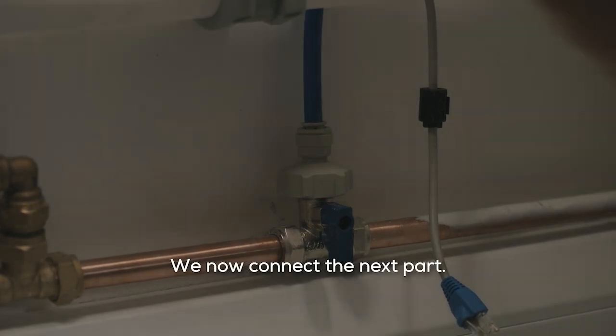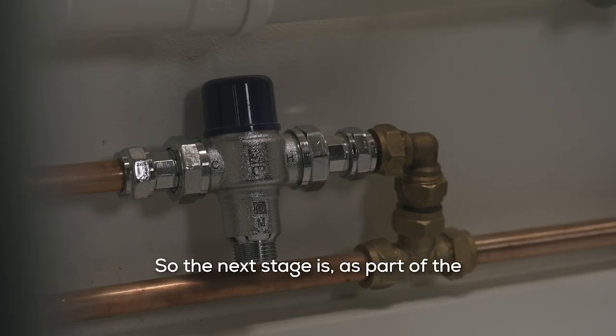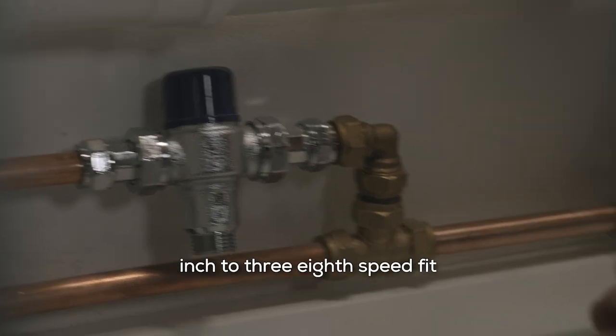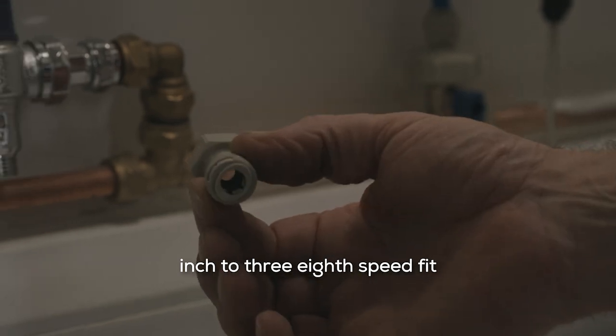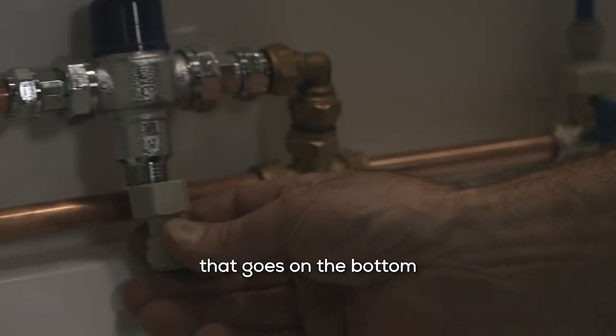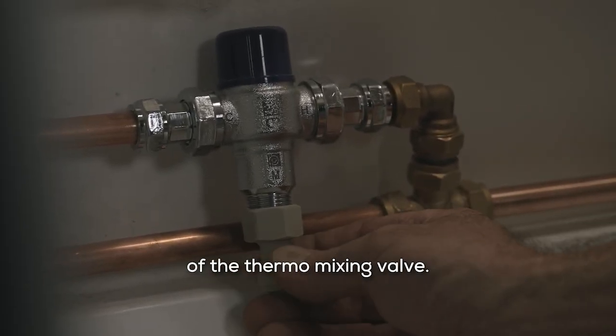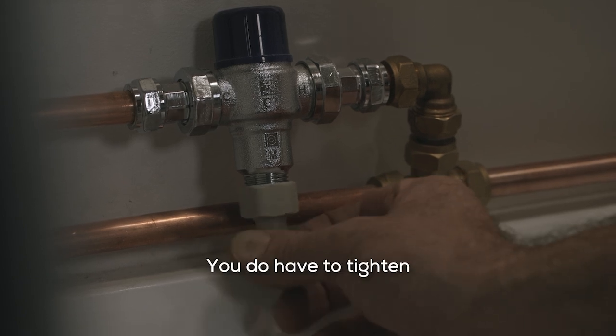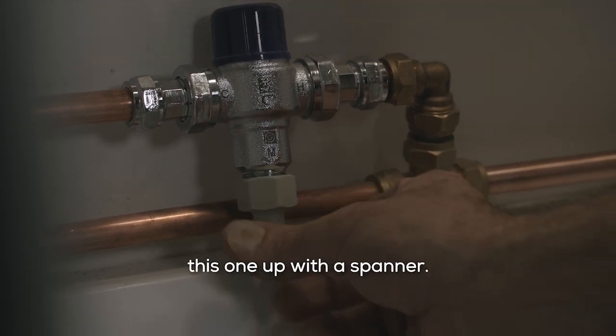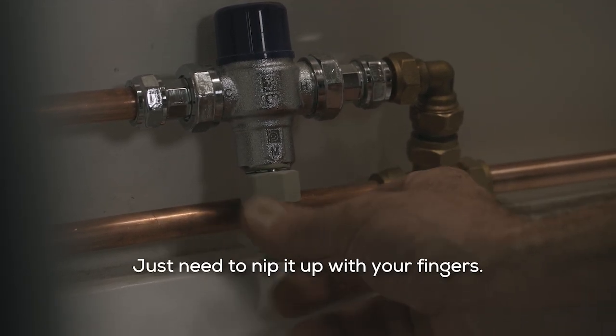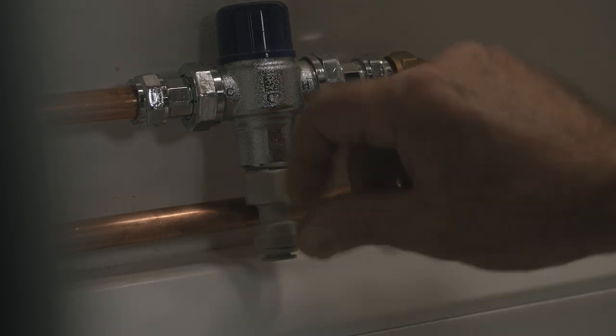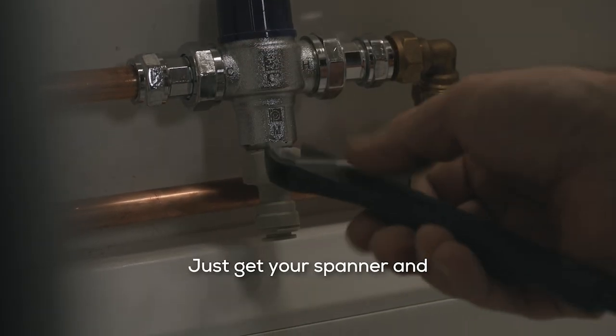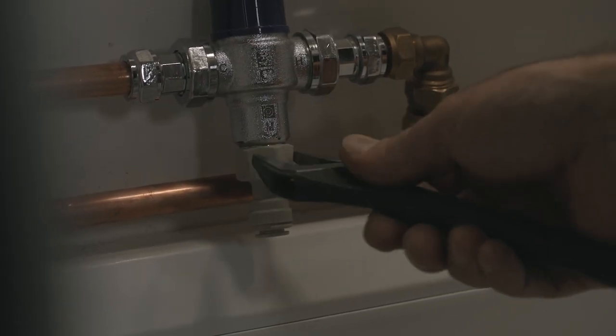We now connect the next part. So the next stage is, as part of the supplied install kit, you'll have a 1/2 inch to 3/8 speed fit that goes on the bottom of the thermomixing valve. You do have to tighten this one up with a spanner. Just nip it up with your fingers. Then get your spanner and give it a couple of turns.